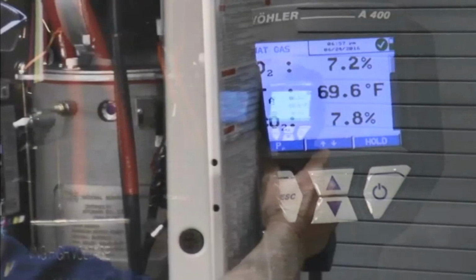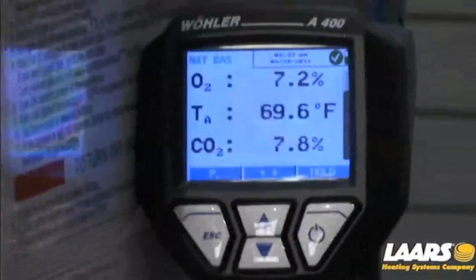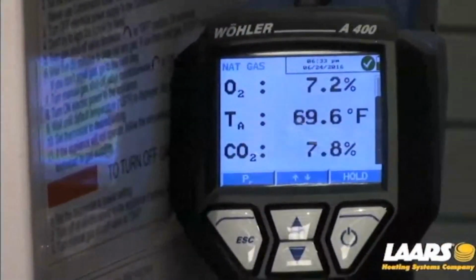CO2. Most manufacturers go by CO2. There are a couple out there that go by O2. So make sure you read your manufacturer's instructions, okay? We go by CO2. Looking at our analyzer, we can see we're well below that. So we need to make an adjustment.